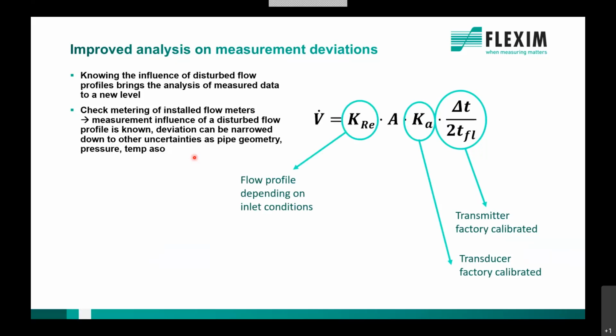And when knowing the flow profile, that's depending on the inlet conditions. We know the flow profile now. We know the distance. We know the effect. That means we know the error, which is compensated. That means these 3 factors, at least in our flow volume formula, are known. That means uncertainties are very low. What's left is the pipe geometry. That needs to be measured in the field because the clamp-on meter becomes a flow meter when it's installed in the field and not before. What can you do to keep that uncertainty low? Well, you measure the circumference and the wall thickness, then you know the inner diameter. So if all these factors are known, the volume flow must be correct.